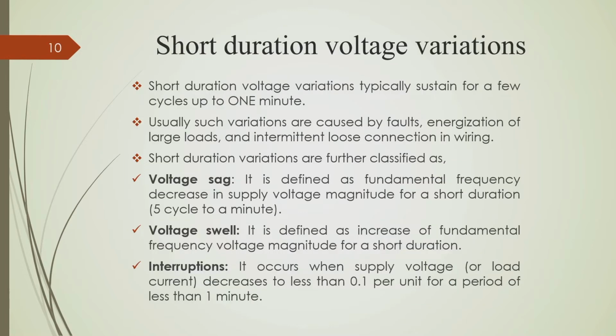Okay. Now, we will come to short duration voltage quality problem or short duration voltage variation. As I said, this short duration stands for few cycle, from half a cycle up to 1 minute. So, if there is a voltage quality problem which lasts a maximum of 1 minute, we will categorize it as short duration voltage variation. This occurs due to faults; single line to ground fault is the most common cause for this type of voltage variations, and they have some significant impact.